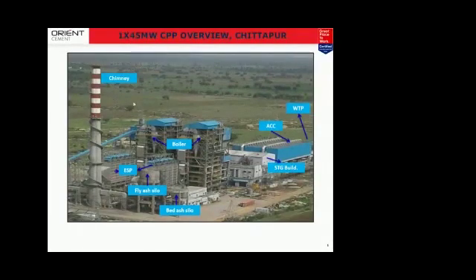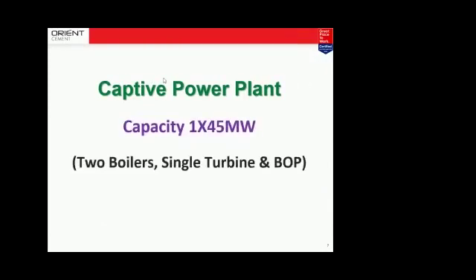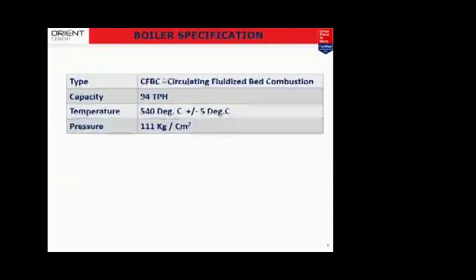As you can see, we are operating with two boilers and a single turbine. Our captive power plant is quite different from other plants since we are operating with two boilers and a single turbine combination. Usually you don't see this combination. This is a very rare combination which was tried over here. Each boiler is a circulating fluidized bed combustion boiler, that is a CFBC boiler, and each boiler has a steam generation capacity of 94 TPH.